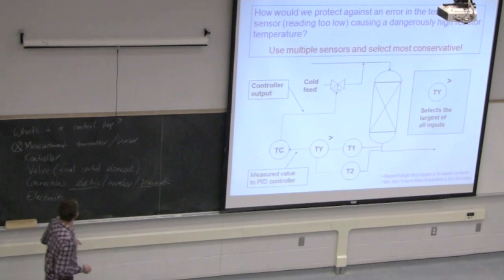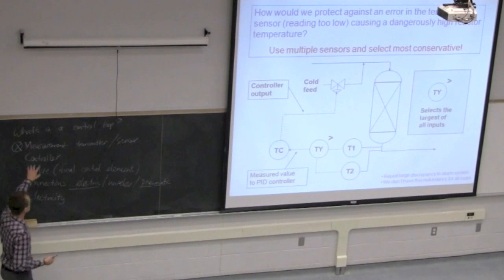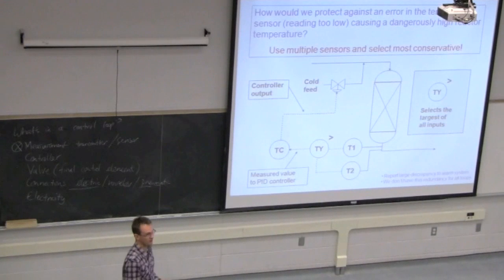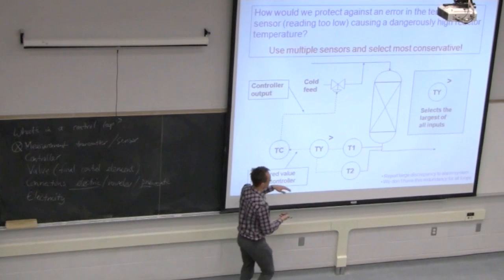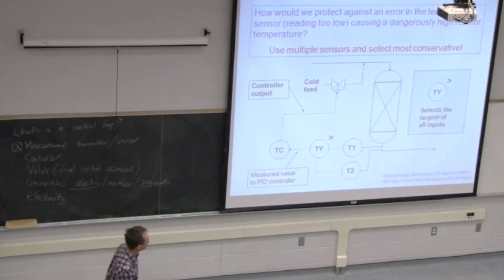So whenever we have these issues of potential failure and reliability of either the measurement sensor, the controller, the valve, our standard approach is to put on a second one. Okay? So if we're concerned that our valve may fail, we can put in parallel feeds with two valves. If we're concerned our sensor is going to fail, we put in two sensors. Nuclear industry will often put three or five sensors, and they pick the best three out of five to control on. So control loops that absolutely cannot fail on us, we put on greater and greater levels of redundancy, and then have a voting system in place where we pick the sensors that agree most with each other, and it's a democratic decision that gets used in control. So that's the principle there.